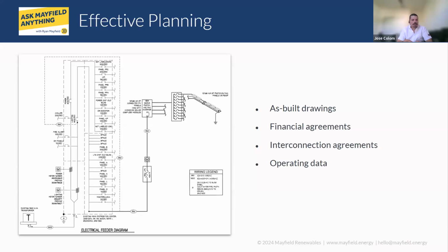I agree on this one. The main thing we ask for is as-built drawings—we need to look at it, especially with the team we have in-house looking at the as-built drawings. We look into the details, going back to the previous slide talking about inverter topology and the system voltages—we look into those details. We need to know what we're working with. I'd say we typically start on the DC side and work our way all the way to the AC side of the system in order to determine the ideal inverter.